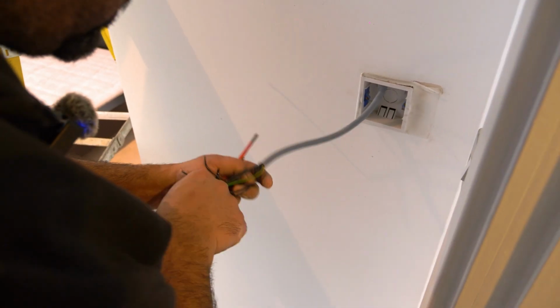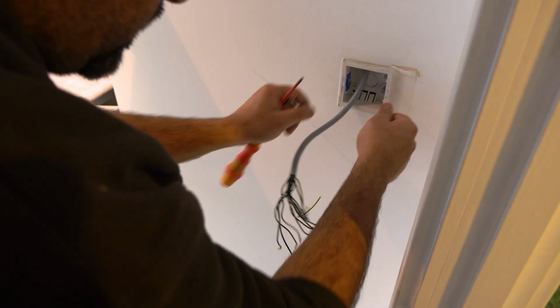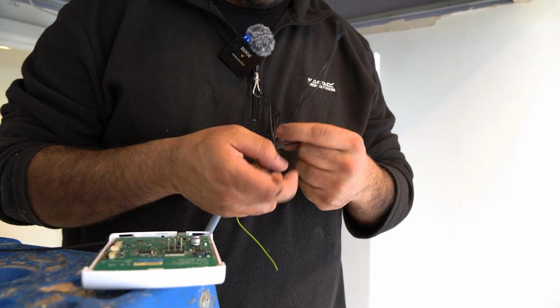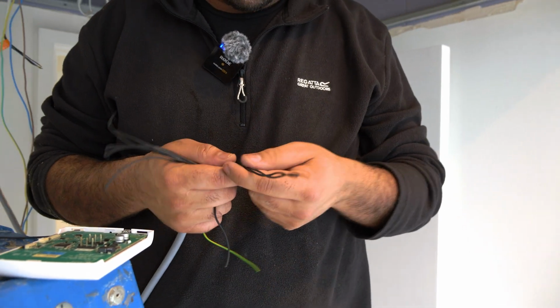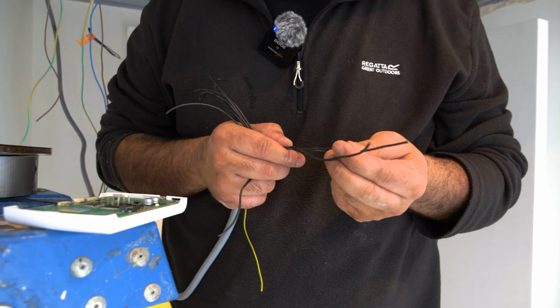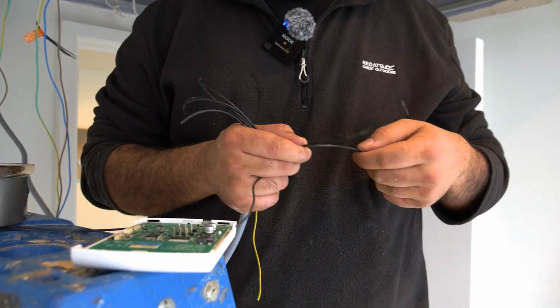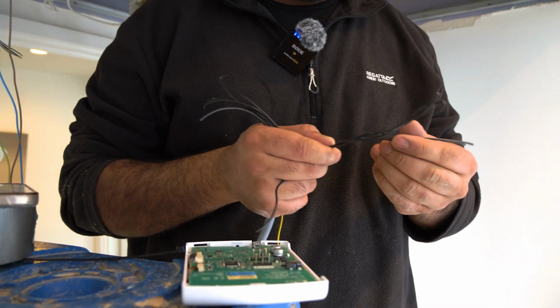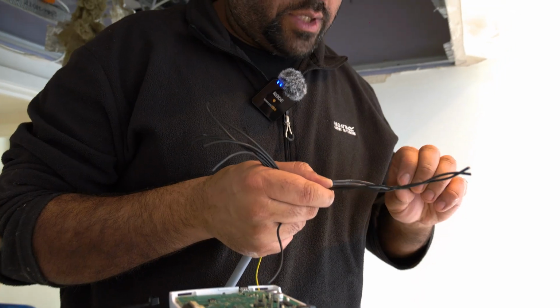You can see all our cores here. So that and that's all we need for the controller. 1 and 2 is taped together. That's going to be my communication 1 and 2 from the fan coil, and 3 is going to be my 24 volt DC and 4 is going to be my ground, and I'm going to chop the rest of it off.